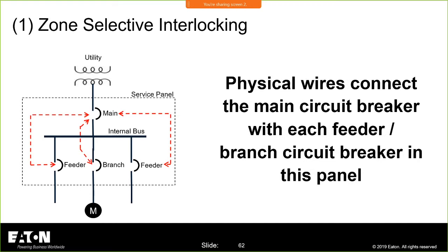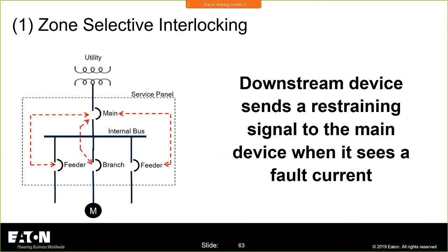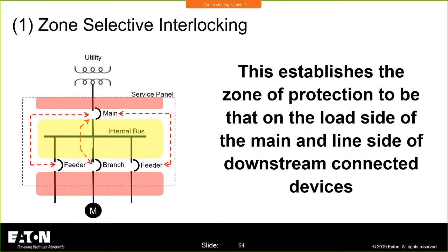The way we wire these up, we wire them all together. This is the most simple configuration. And the zone of protection is right there. If I have a fault down here and I didn't coordinate these two devices, and the fault current is greater than the instantaneous pickup of that feeder breaker and greater than the instantaneous pickup of that main device, they will both open. I don't care about ZSI. They will both open. What ZSI gets you is when I have a fault inside here, that's when this main device ignores the settings that you gave it for selective coordination and goes without an intentional delay.